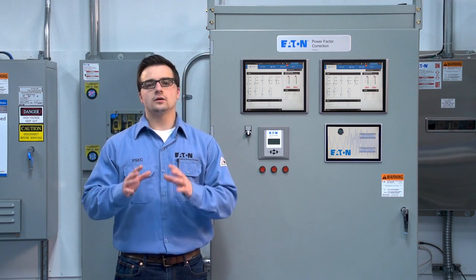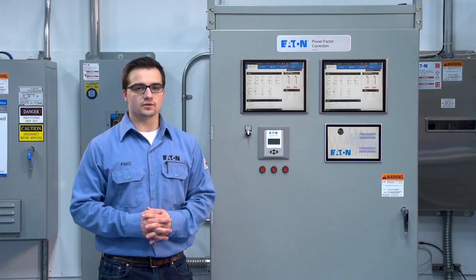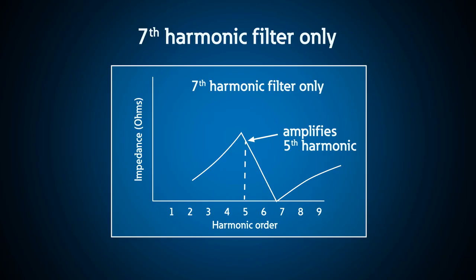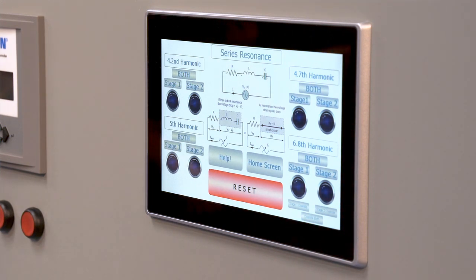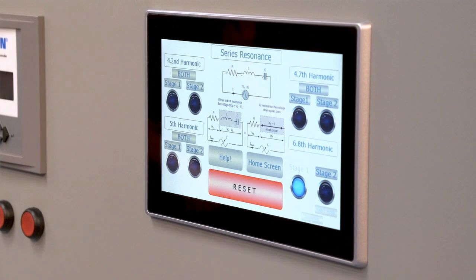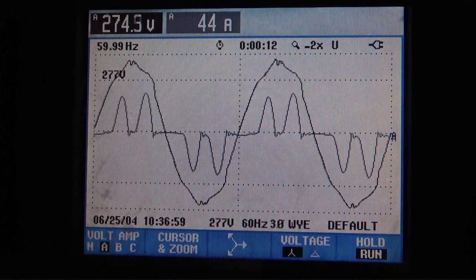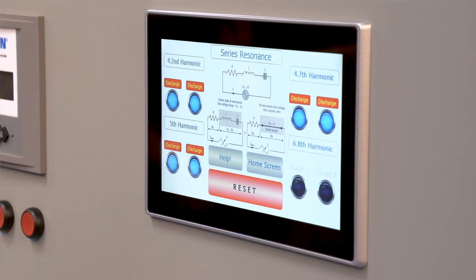To convey that point, I'll show you what we can do on the demo unit using the 7th harmonic filter without the 5th harmonic filter. Remember when I talked about the fact that we never want to turn on the 7th harmonic by itself? Well, here we actually put in a button where we can have an override and turn on the 7th harmonic by itself — but we do have a safety where it will turn off after five seconds. So here I'm going to turn on the stage 1 override. Now the 7th harmonic filter is on — right now we are filtering 7th harmonic current but we're actually enhancing the 5th harmonic. And now the five seconds is up and all of the capacitors are going to make sure that they are discharged.